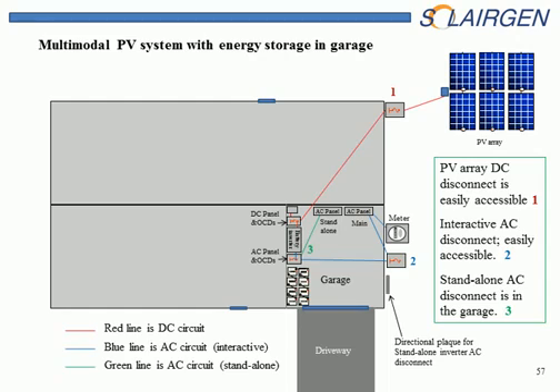Here is a similar scenario. We have another multimodal system, but instead of in the basement, we have the batteries and the battery inverter located in the garage. So your critical loads panel is in the garage, for standalone, and all of the equipment is too. Now that would be easier to identify. You probably have more visibility, more access. It would really depend on where the emergency was in the structure. And hopefully you would have all your disconnects outside. The DC, since this is a ground mount, is your most important. The AC just shuts down any power usage or any AC power being produced. Here again, the critical loads panel, a standalone panel, disconnect may be inside.